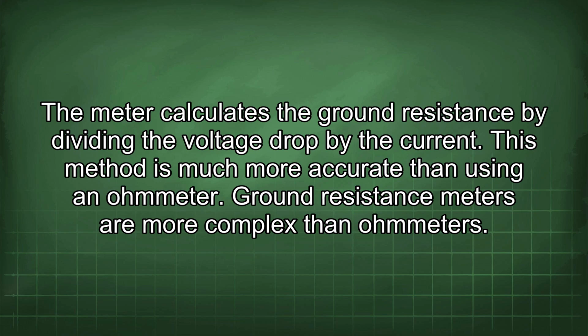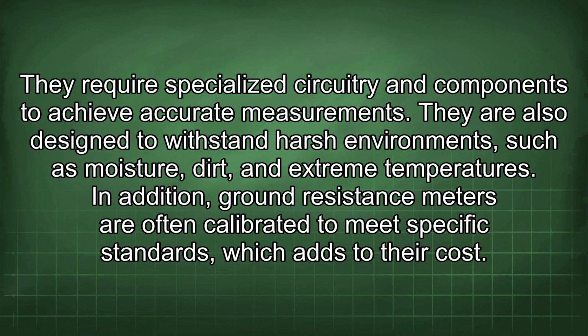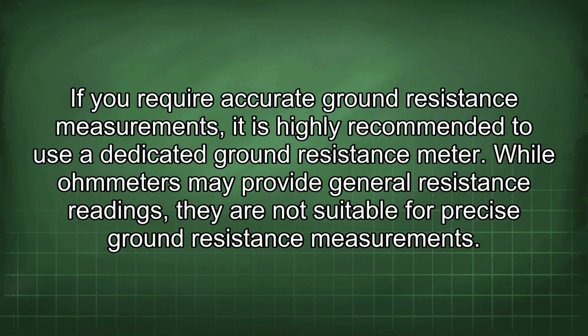Ground resistance meters are more complex than ohmmeters. They require specialized circuitry and components to achieve accurate measurements. They are also designed to withstand harsh environments such as moisture, dirt, and extreme temperatures. In addition, ground resistance meters are often calibrated to meet specific standards, which adds to their cost. If you require accurate ground resistance measurements, it is highly recommended to use a dedicated ground resistance meter. While ohmmeters may provide general resistance readings, they are not suitable for precise ground resistance measurements.